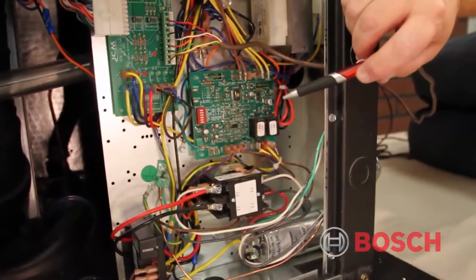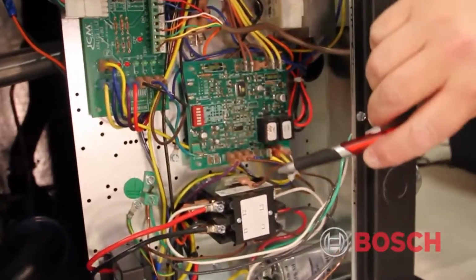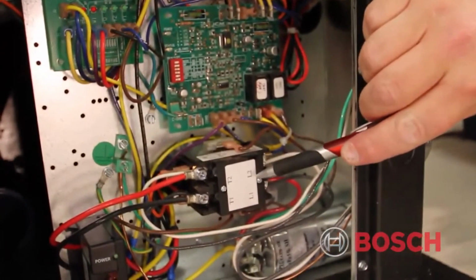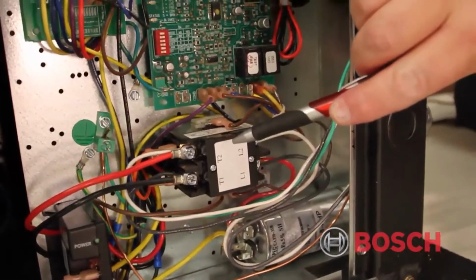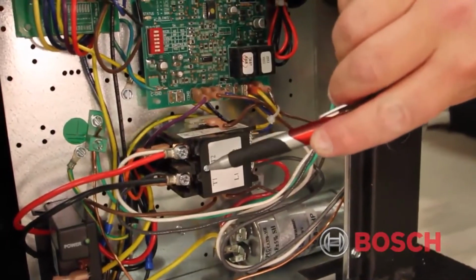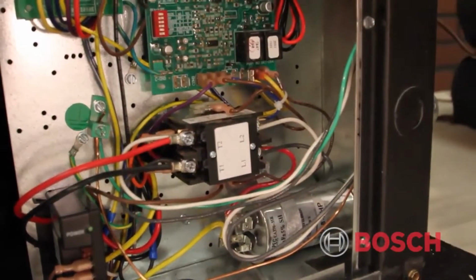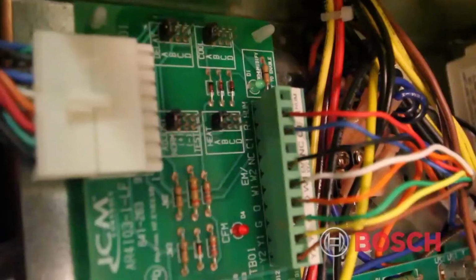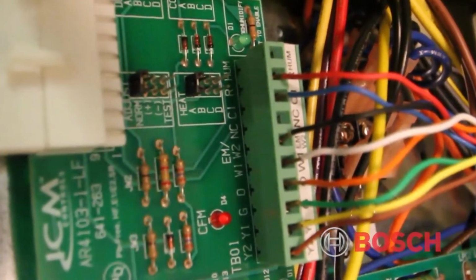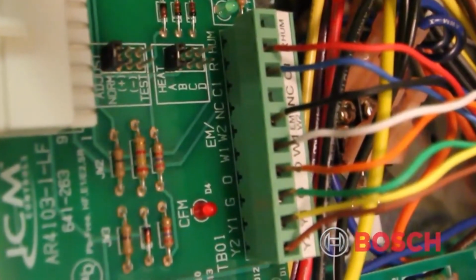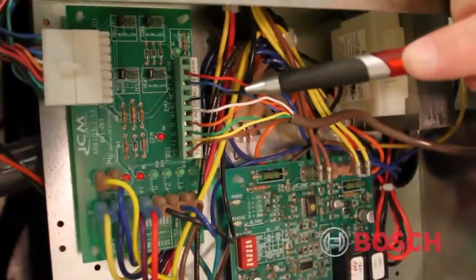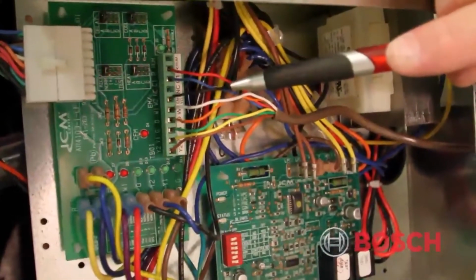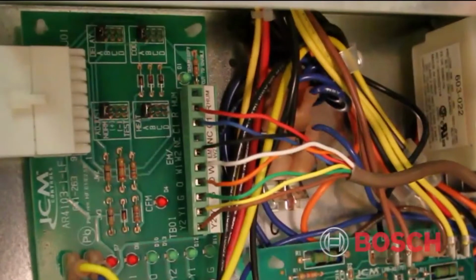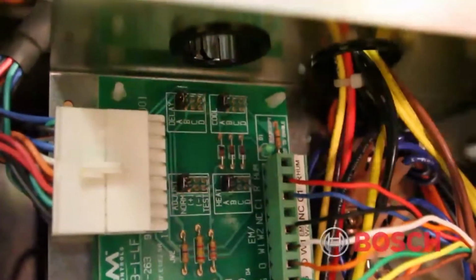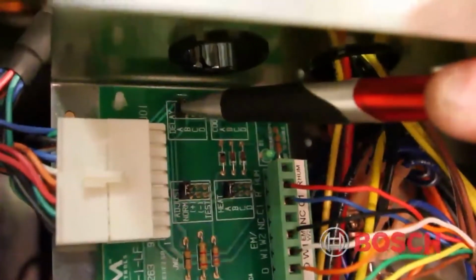You can see at this point that we've made our high voltage connections at L1 and L2 from our power supply. We've also made our circulating pump connections at T1 and T2. Up here on our ECM motor control board, our low voltage connections are completed. At this point is a good time to go ahead and set up the dip switches and the jumpers on our control boards. On the ECM motor control board, you have 4 sets of jumpers. You have an adjust jumper, you have a delayed jumper, you have a heating jumper, and a cooling jumper.